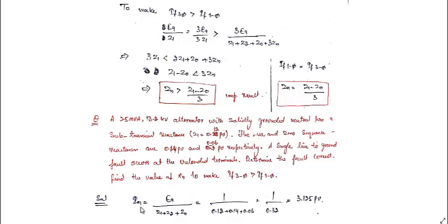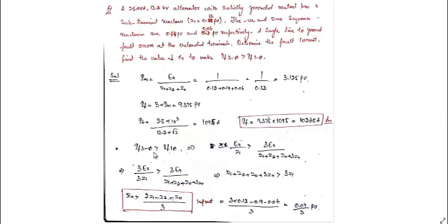So first we will calculate simply IA1, that is EA divided by Z1 plus Z2 plus Z0, which is given on its own rating as 0.12, 0.14, 0.06. It comes out to be 3.125 per unit. So IF is equal to 3 times IA1, that is 3 into 3.125, which is 9.375, and the base current will be equal to 25 into 10 to the power 3 divided by 13.2 into root 3, which comes out to be 1095 amperes. So IF will be equal to the per unit value multiplied by the base value, that is 10.265 kiloamperes. So this is the fault current.